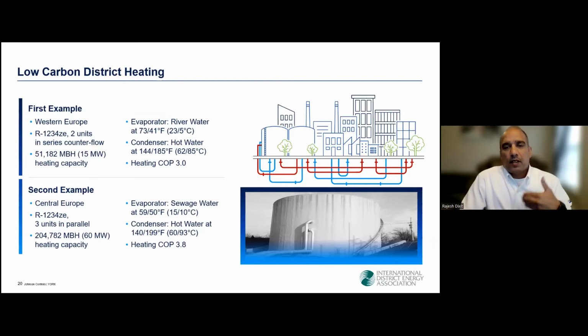The second example is underway in Central Europe, involving 3 large, or I should say super large, high-head multi-stage centrifugal heat pumps, recovering the heat from the municipal sewage to deliver 199 degrees Fahrenheit, 93 Celsius for district heating. In this case, the heating capacity is 200 million BTUs with a heating COP of almost 3.8. In both examples, you can see that the refrigerant is R1234ZE with a GWP of less than 1.0, GWP meaning global warming potential.